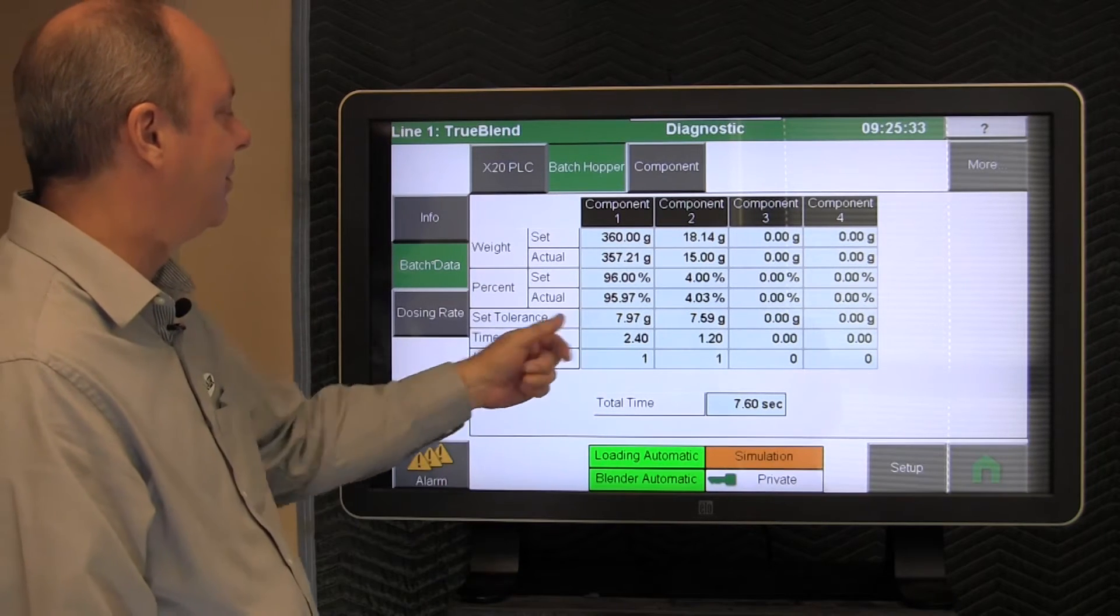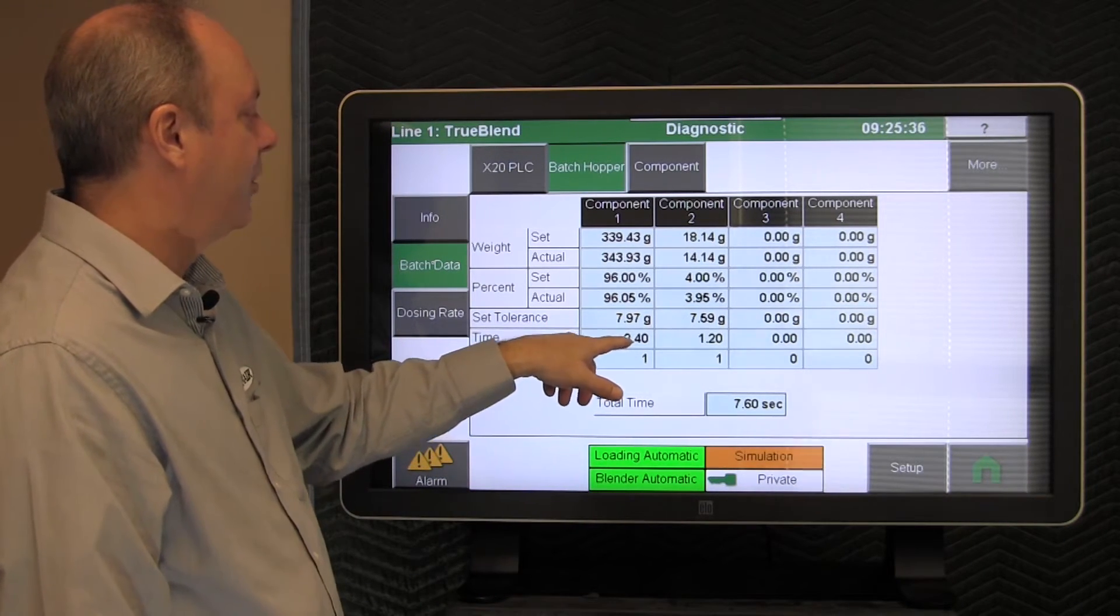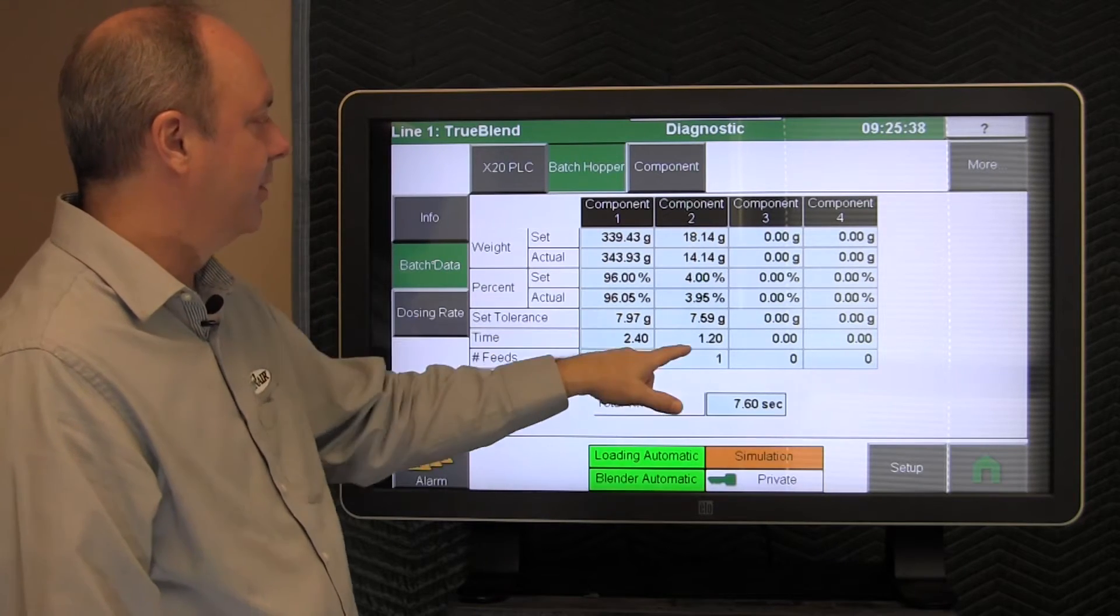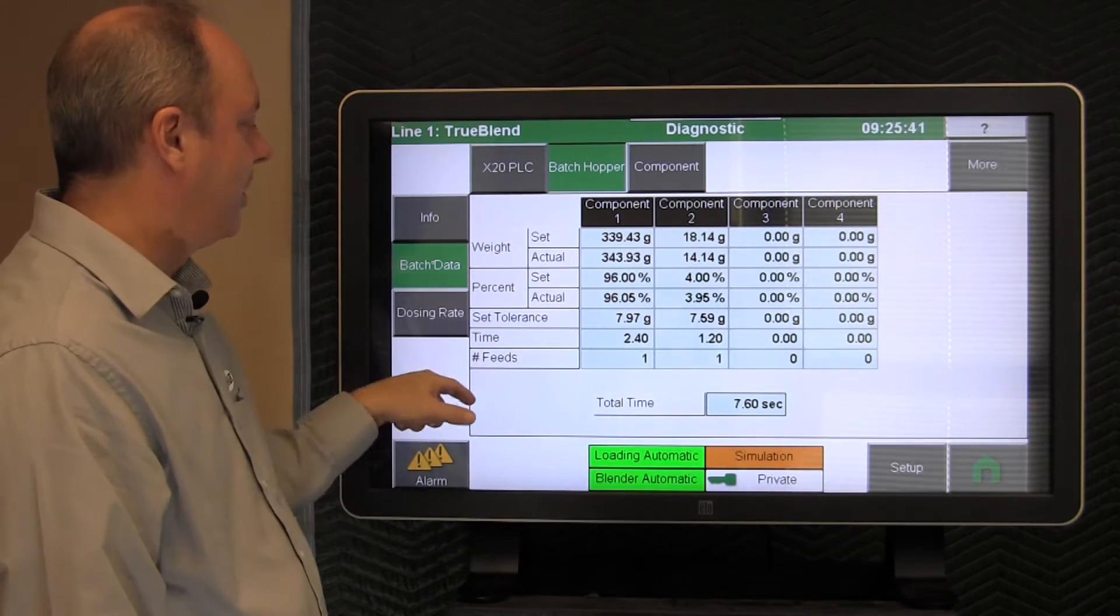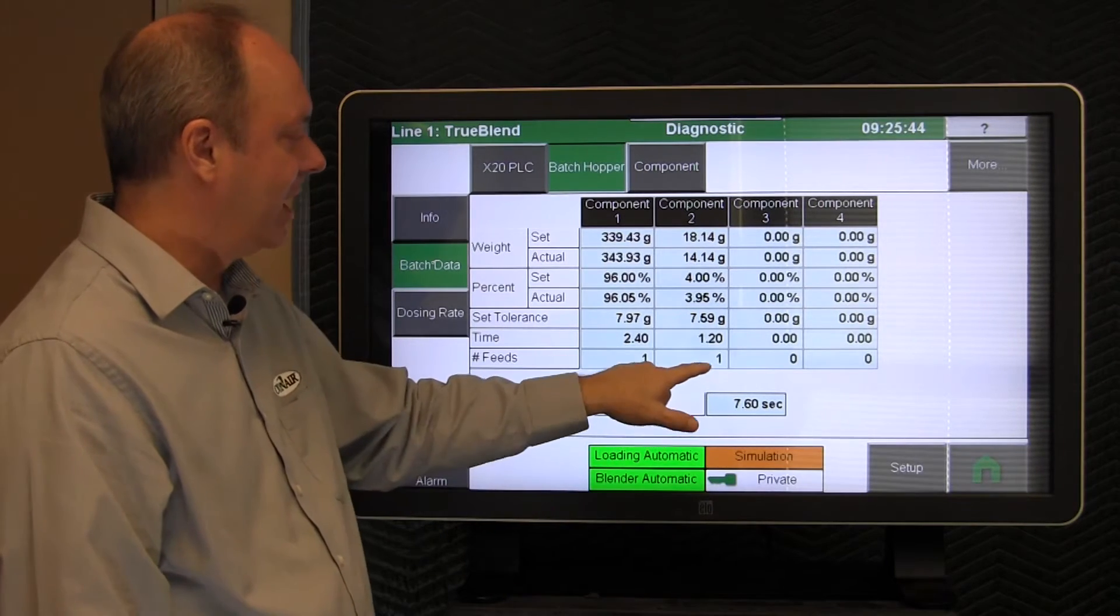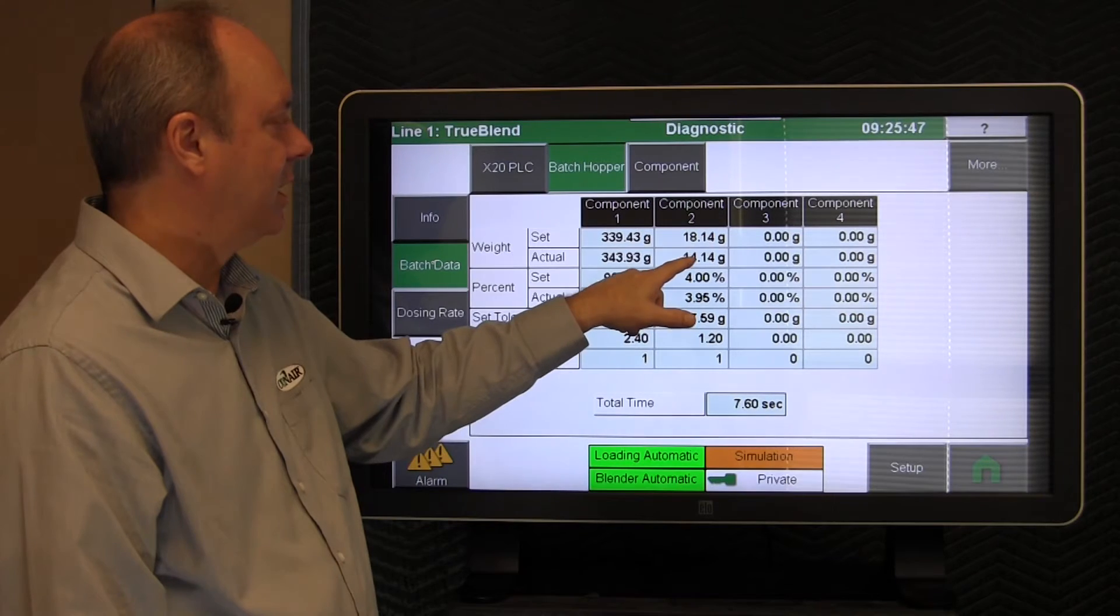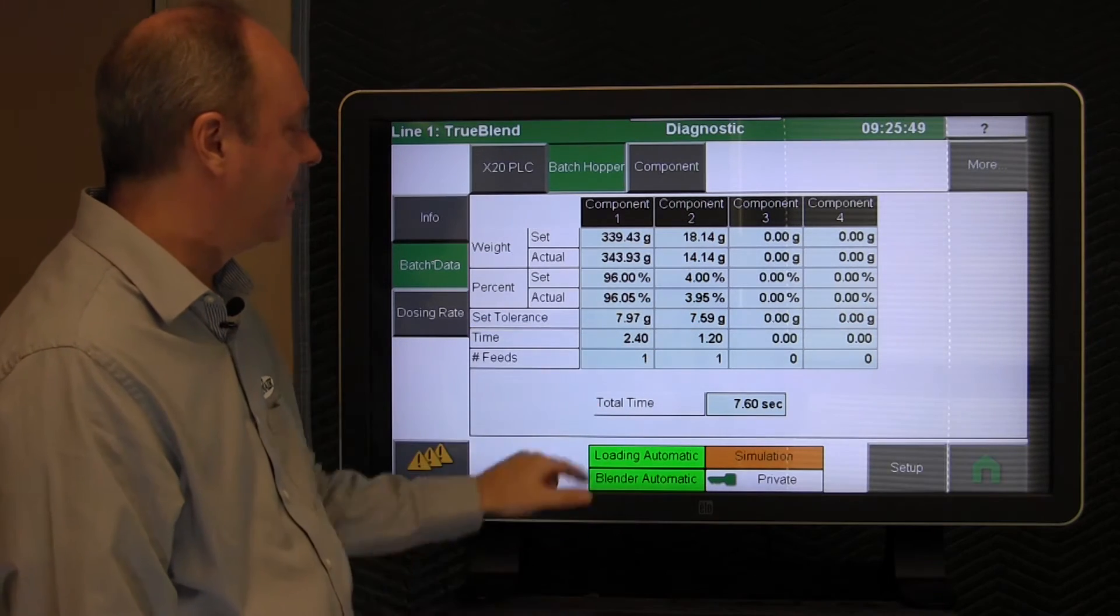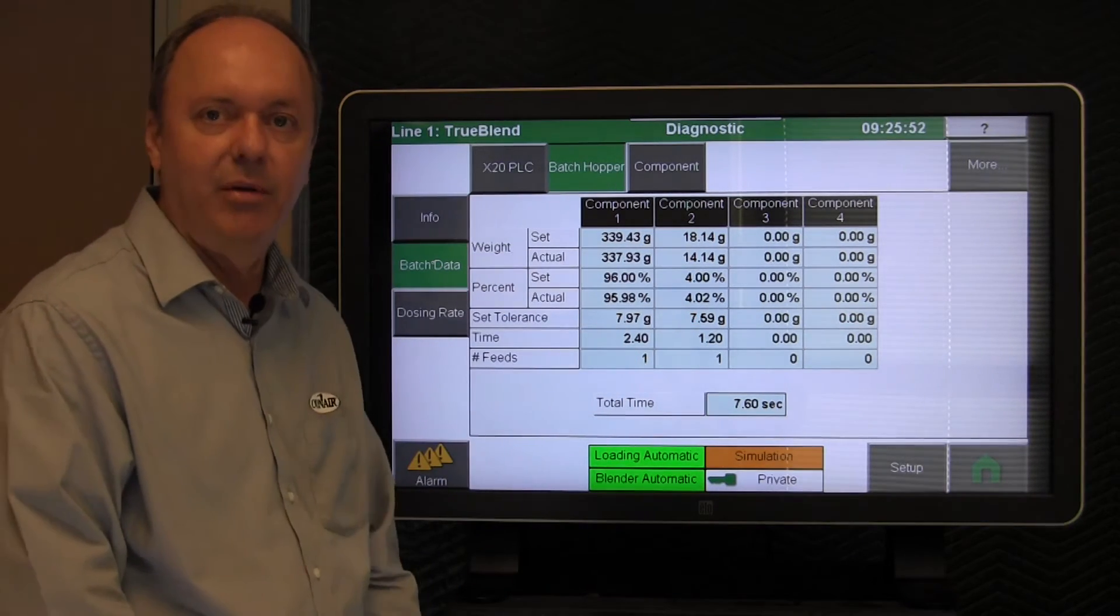The time below that is the amount of time it takes, 2.4 seconds to dose that material. This one takes 1.2 seconds. And then below that, the number of feeds. In this particular case, we're taking one dose to hit the 14 grams that we had there and one dose to hit the 338 grams shown there.